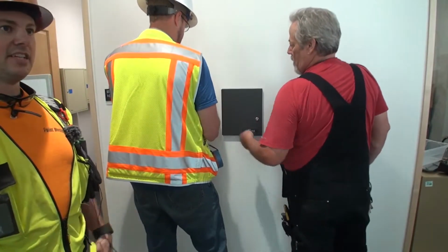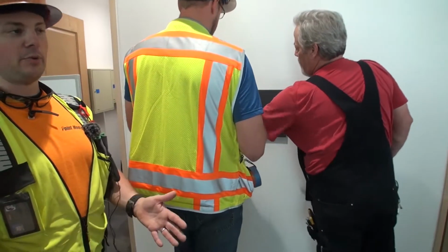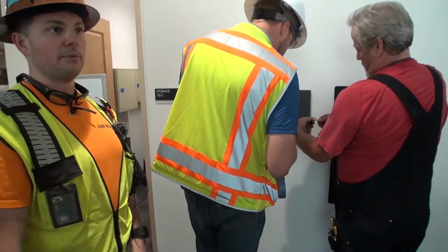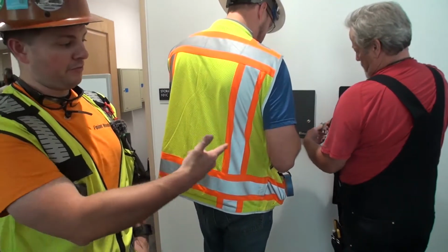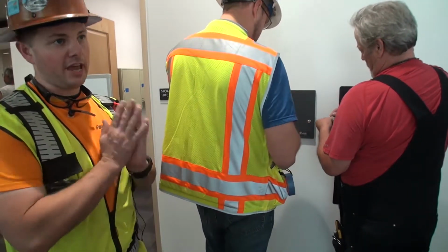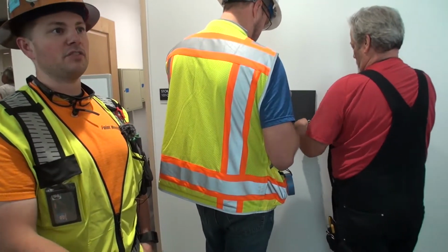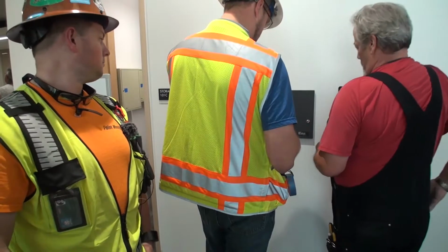On a voice evac system, it'll give you the automatic message evacuating the building, but if somebody needs to give specific instruction to the building, they could pick up and from here it'll be a global message to everyone. Down below at the main fire panel, you could isolate it to a specific zone. Gotcha.